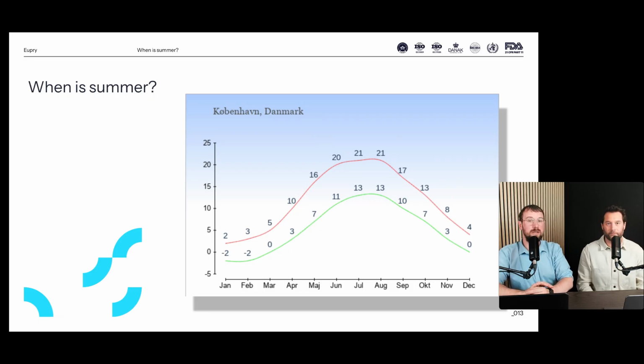We're not only trying to define whether the facilities or temperature controlled units can handle specific temperatures during summer, but also trying to get information on how we should monitor afterwards. It's not that if it operates well at 25 degrees it will also operate well at 30 degrees. Instead, you get information on where the hot spots and cold spots are in the facility during these conditions. When you place constant monitoring in those positions and the temperature rises, you should be able to see whether you're experiencing non-compliant temperatures. So the key point is we're doing point-in-time measurements, but also trying to assess where we should monitor afterwards.